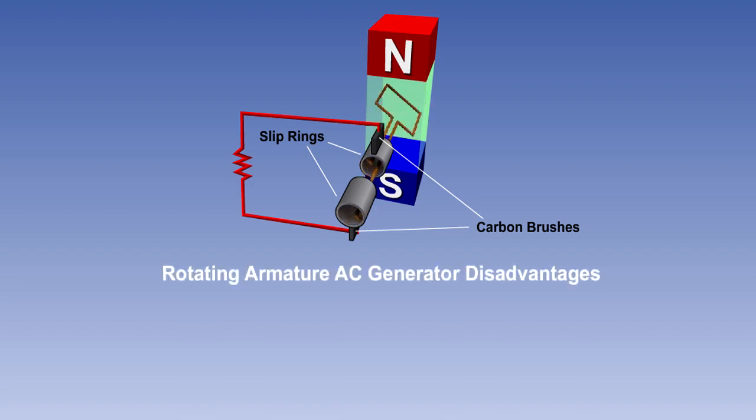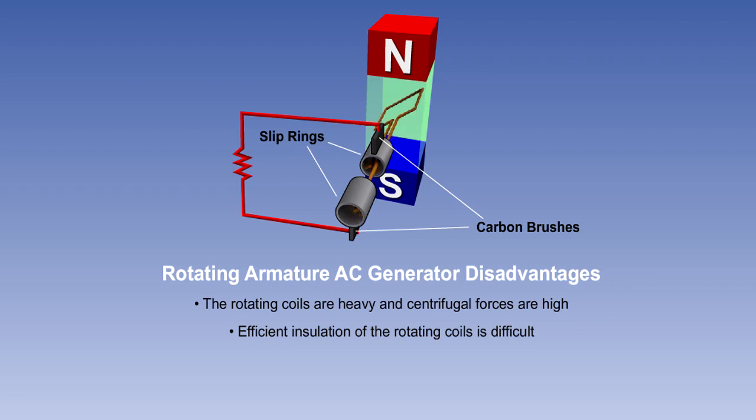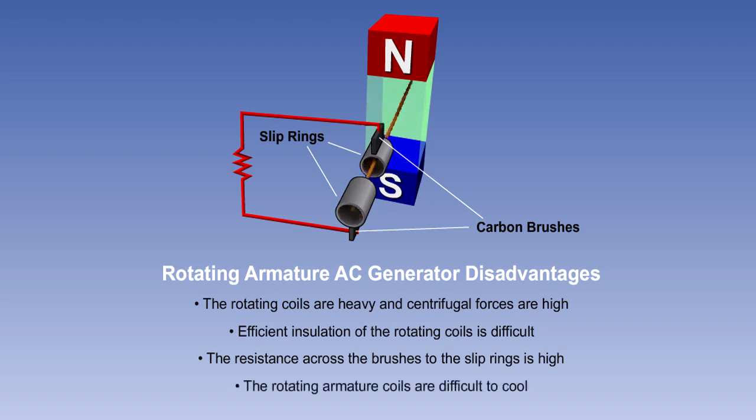Rotating armature AC generators suffer from a number of disadvantages. The rotating coils are heavy, and centrifugal forces are high. Efficient insulation of the rotating coils is difficult. The resistance across the brushes to the slip rings is high. And the rotating armature coils are difficult to cool.